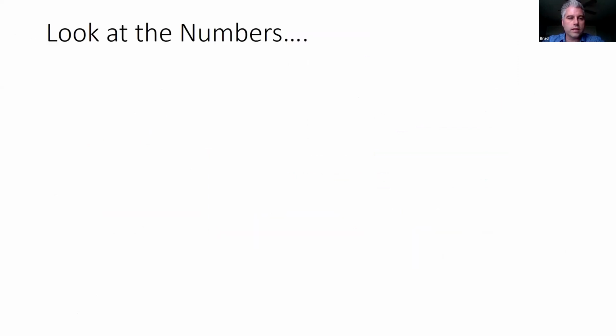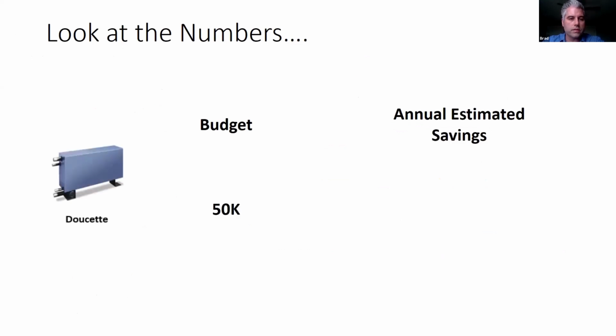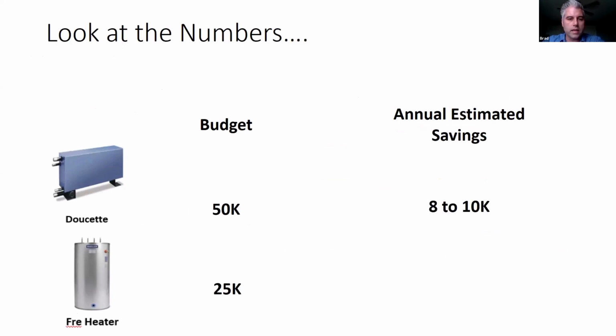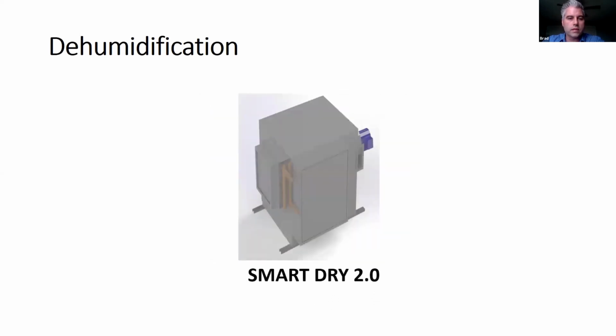Let's look at the numbers for the Doucette and the free heater. The budget to install a Doucette is around $50,000, and for a free heater around $25,000. The annual estimated savings for a Doucette is $8,000 to $10,000 in gas savings a year, and for the free heater, $3,000 to $5,000. Another option to consider is installing dehumidification and recovering waste heat to improve the efficiency of the dehumidifier.